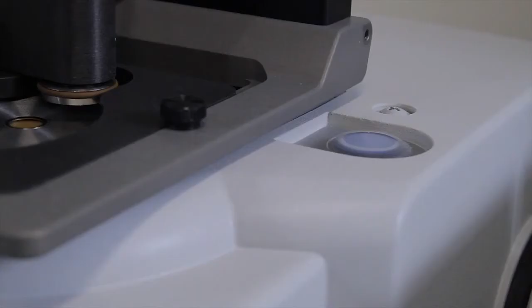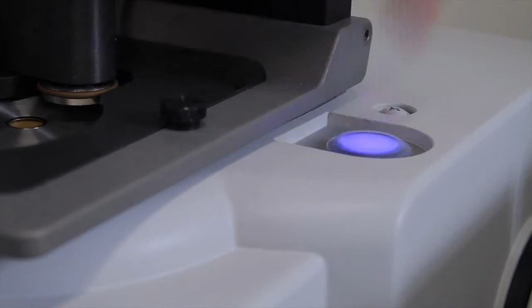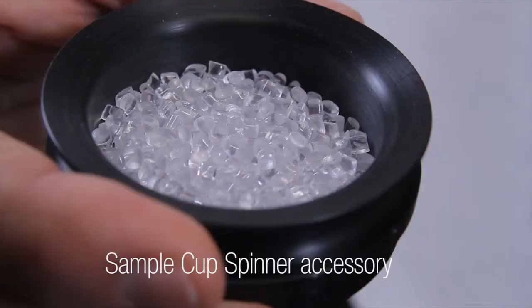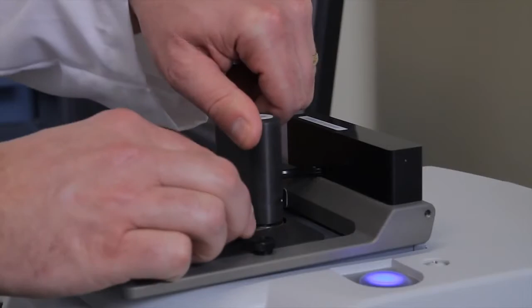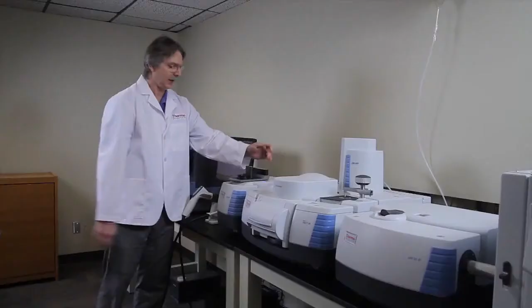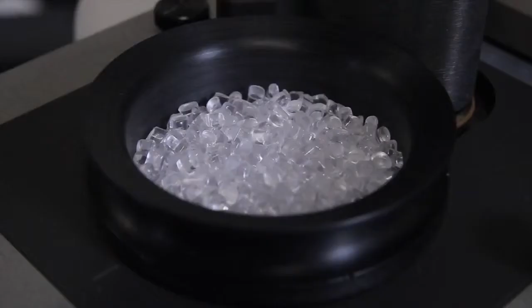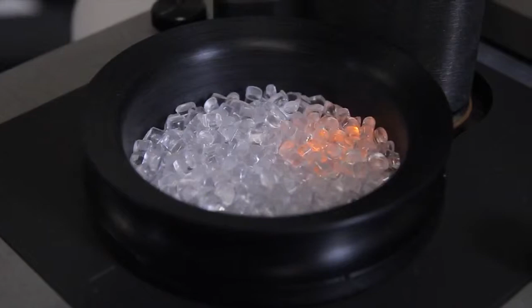What I'd like to do then is show how we can collect polymer spectra using the integrating sphere. Once again, all we need to do is push the button. A background spectrum is collected. And once the background spectrum is collected, we can just put our sample on the integrating sphere, and right now I have some polymer pellets that we'll put onto the integrating sphere. We push the button again, the sample cup spinner will spin, allowing you to collect more uniform data, and then when the analysis is done, the spectrum shows up on the screen.